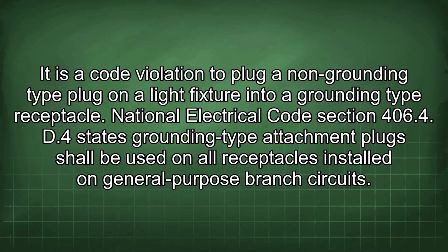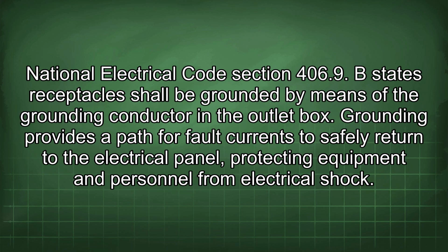It is a code violation to plug a non-grounding type plug on a light fixture into a grounding type receptacle. National Electrical Code Section 406.4 D4 states grounding type attachment plug shall be used on all receptacles installed on general-purpose branch circuits. National Electrical Code Section 406.9 B states receptacles shall be grounded by means of the grounding conductor in the outlet box.